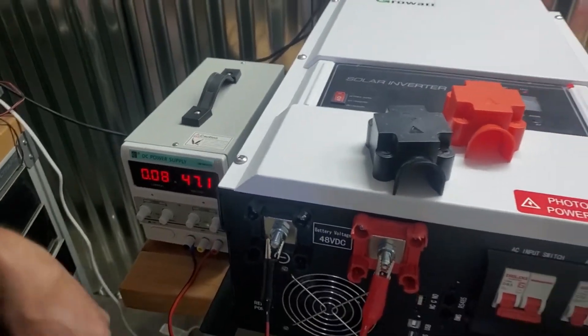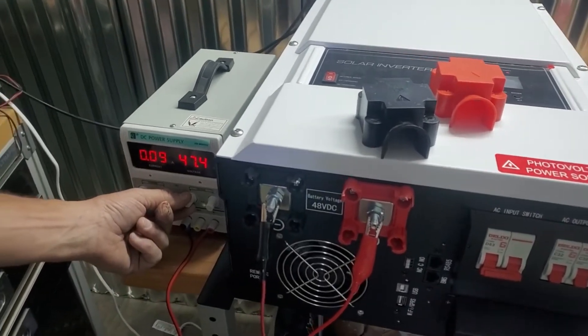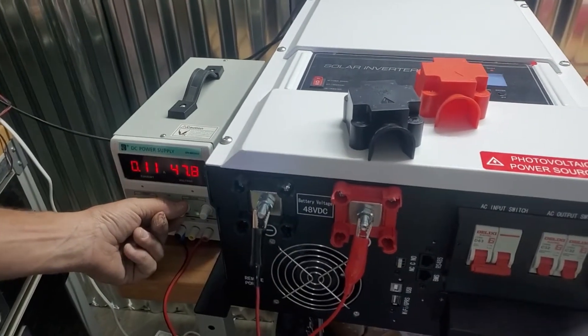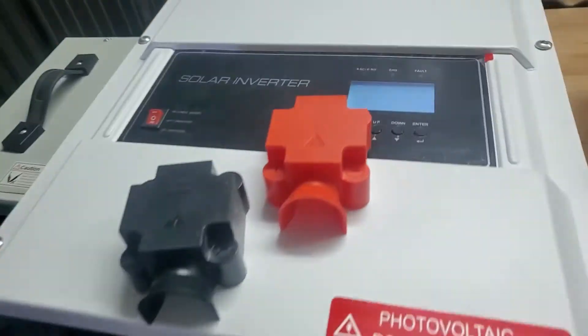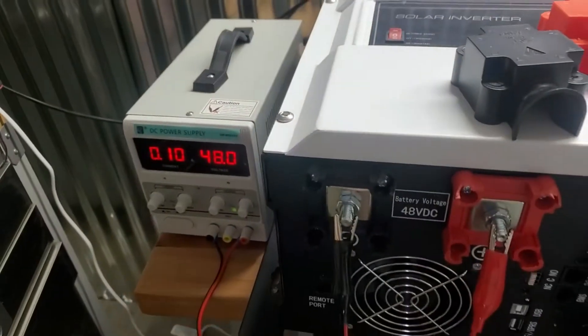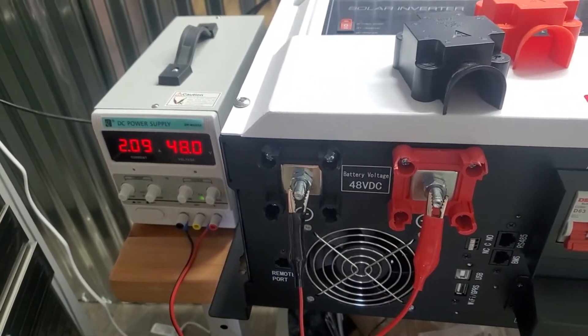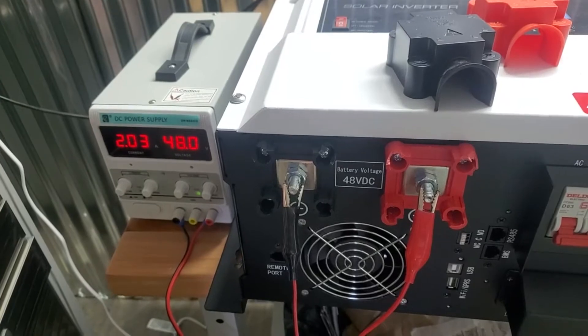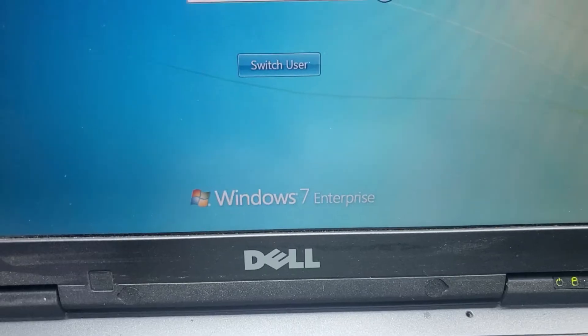Power it up — that's fine as long as it's anywhere from 45 volts to 58 volts. Turning the unit on now. We're reading 48.3 volts, and it draws about two amps on standby with the inverter running. We're running Windows 7 on this — don't run Windows 10.